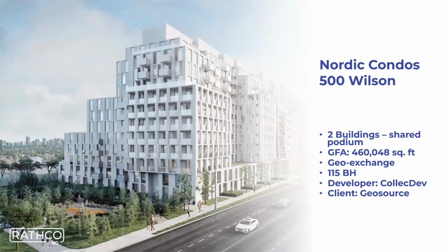Here's some examples. This was one of the first ones we did five years ago. It's now a fully operational building, two buildings, about 500,000 square feet. We did 115 boreholes at 850 feet, about 15 to 20 feet spacing, laid out in a simple grid. We did this with our friends at GeoSource, one of the best drillers in the country. This was a really great first project for us.